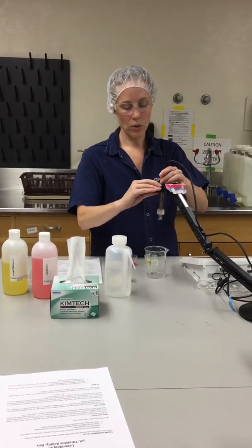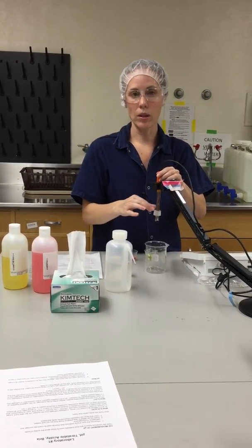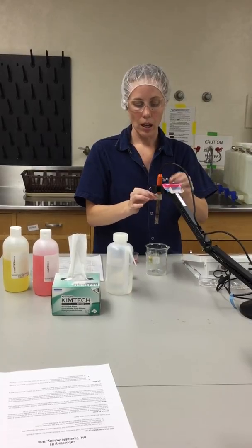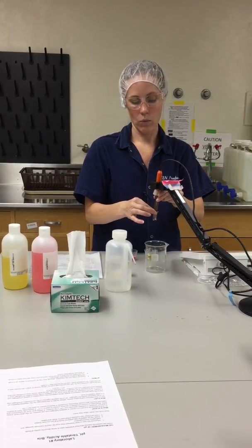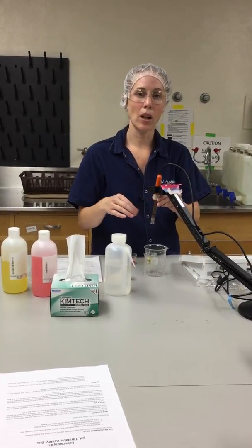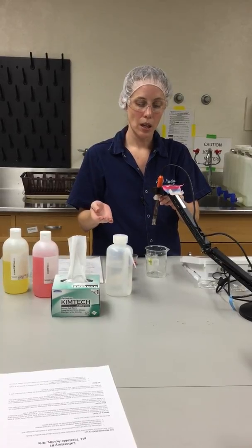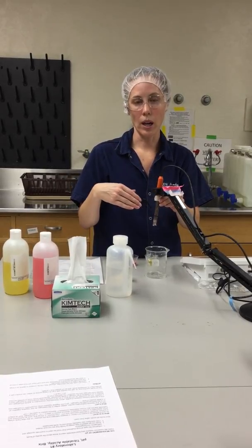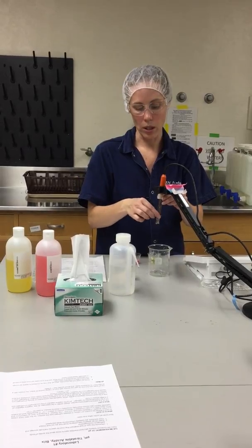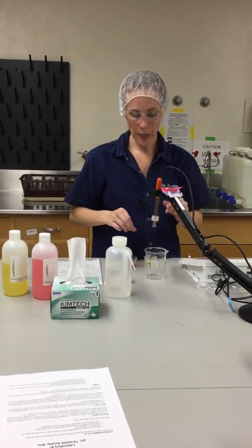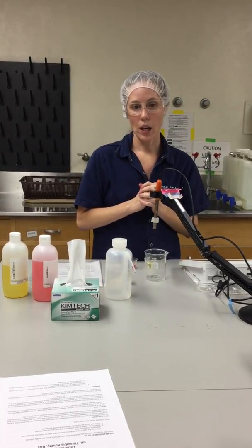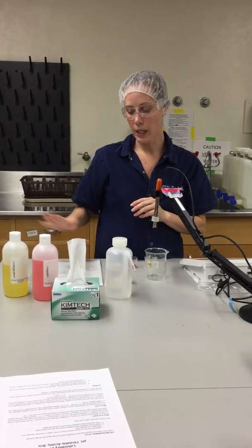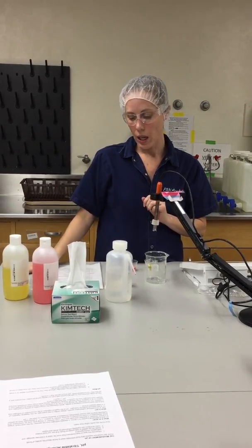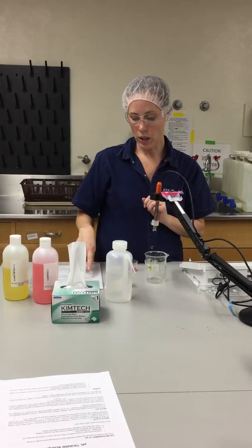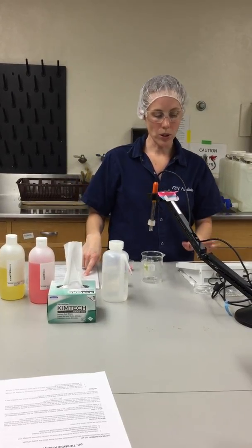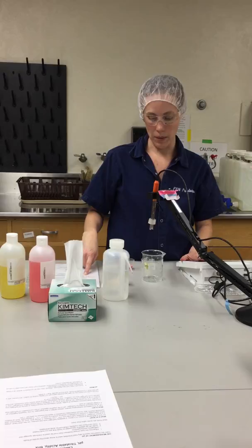So the first thing you're going to do is go ahead and calibrate the meter, and we want the meter calibrated before we work with it. It doesn't have to be calibrated before every reading, but in lab for sure you're going to want to calibrate it at least once before you take your sample readings. What I would suggest doing to make sure that you calibrate appropriately is to have one of your partners read through the instructions as another person uses the machine.